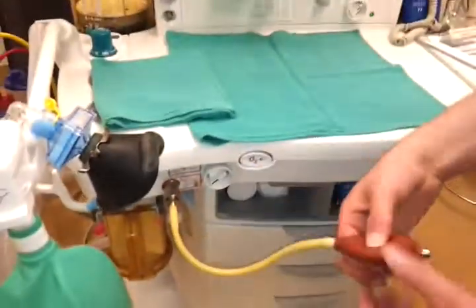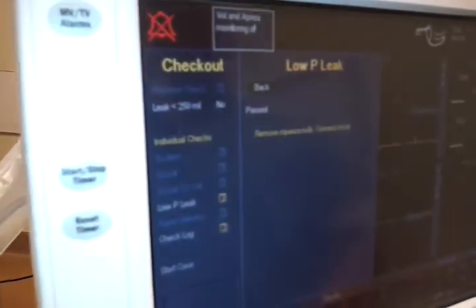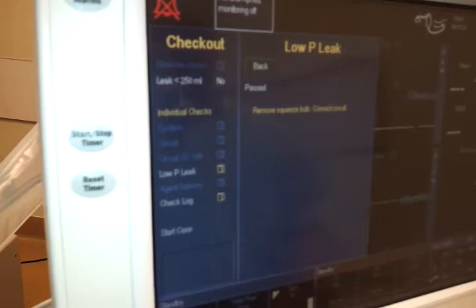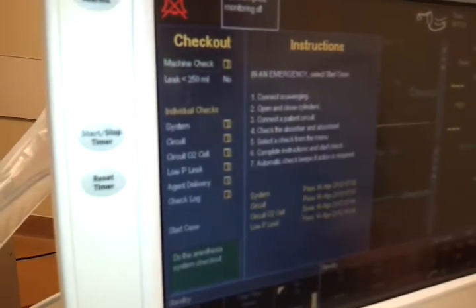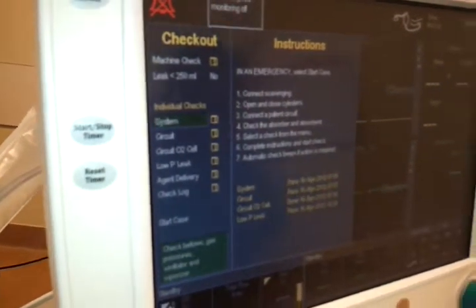So yeah, it's been a minute, and the bulb's still pretty deflated. So all you have to do is hit pass, and that's the low pressure leak test. You flick that off on the gas machine checklist. So you don't need the bulb anymore.